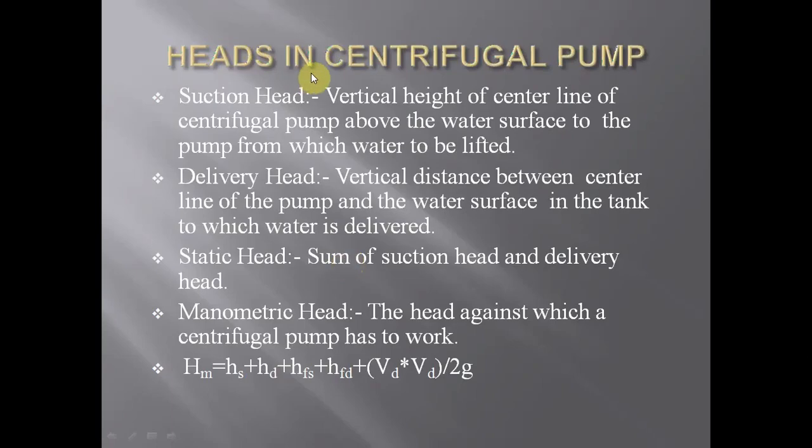So next one is heads in a centrifugal pump: suction head, delivery head, static head, manometric head. Suction head is the vertical height of the center line of the centrifugal pump above the water surface in the sump from which water is to be lifted.